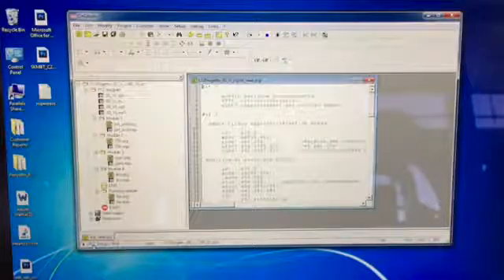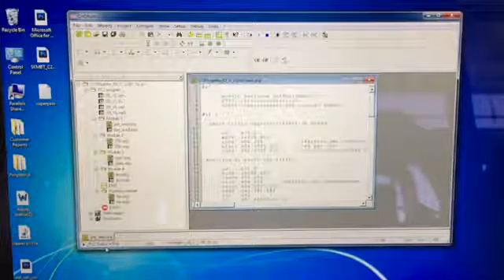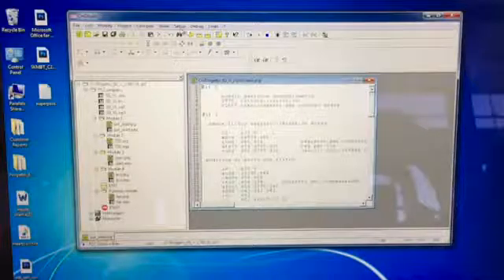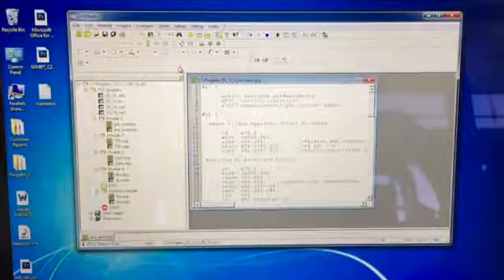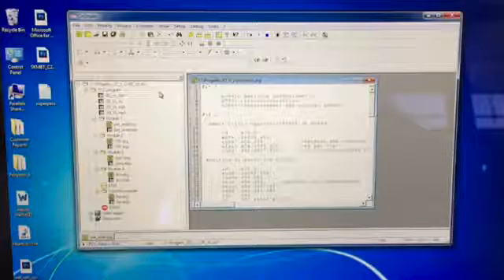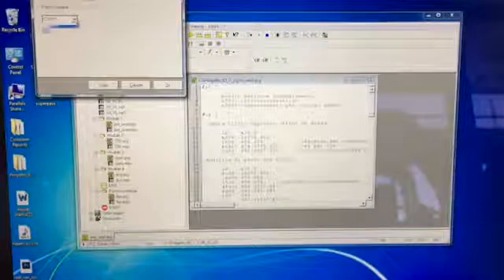Once it opens the project we can see down here in the corner that we have the PLC status is run and that's what we want. If you don't have run you have to check that you are connected with the correct COM port. You can do that again through the setup at the top. If you open the setup and open CM Studio, it will take a minute. Then you can choose Serial.com from the tab and you can click down and choose the port that you want. Mine is port 10 so I'm going to leave it alone.